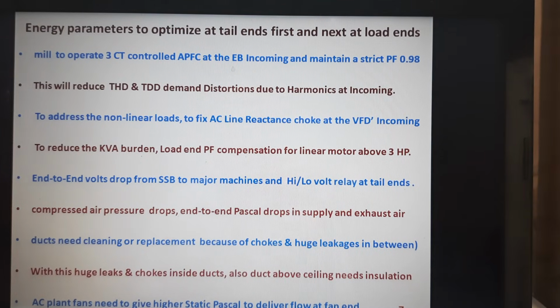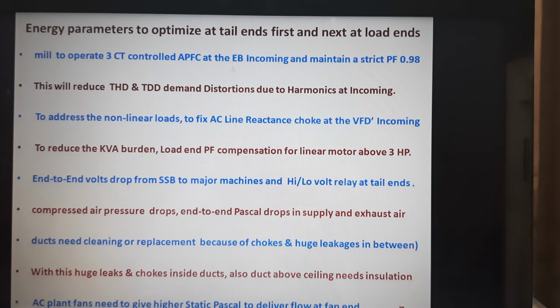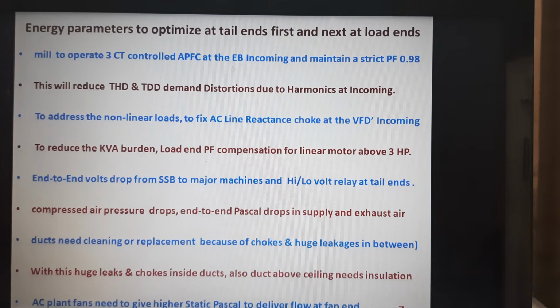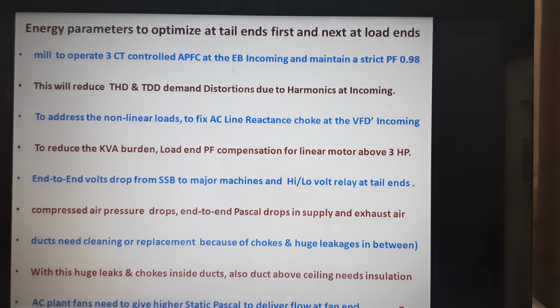The energy parameters are to be optimized at the tail ends first, that is more important, and next to the load ends. First the mill has to see what all the power factor improvements have been done up to the SSB or up to the powerhouse incoming side. Then let us have the 3CT controlled APFC to maintain the power factor at 0.98, precisely at 0.98. Why I am insisting here is, if you go more and more to unity power factor, this leading kVARh increases the unstable voltages at the incoming side, and also the THD and the TDD, total demand distortion, in the harmonics also happens when the power factor goes more than unity. So let us try to maintain it at 0.98 exactly, precisely.